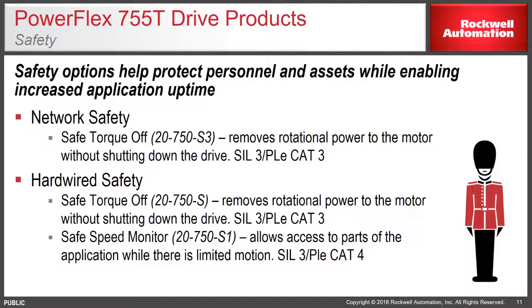Safety. The 755T has network safety with safe torque off with a 20-750-S3, which removes rotational power to the motor without shutting down the drive. This meets SIL 3 or PLE Cat 3.